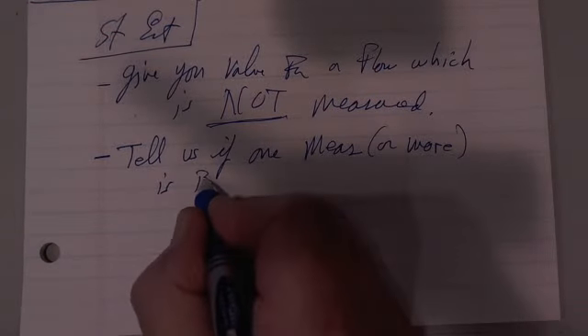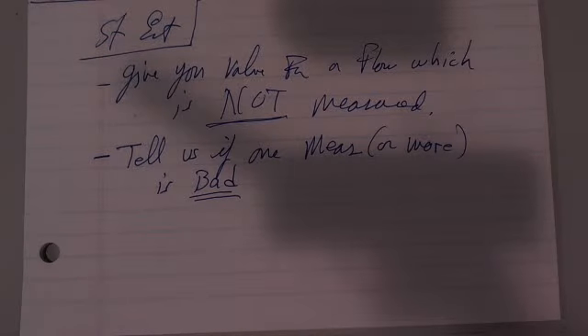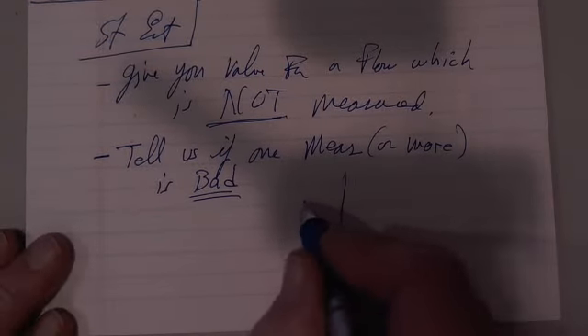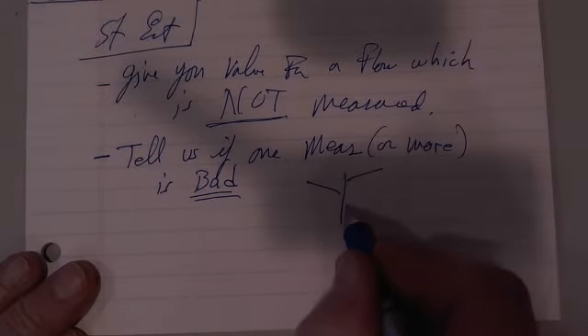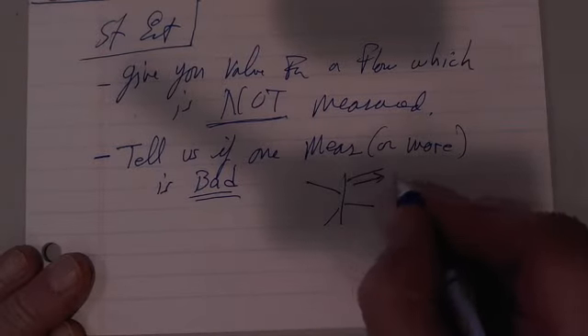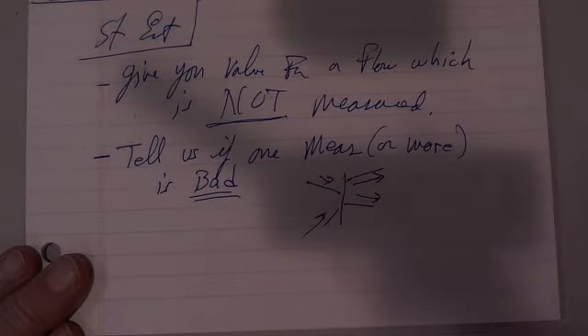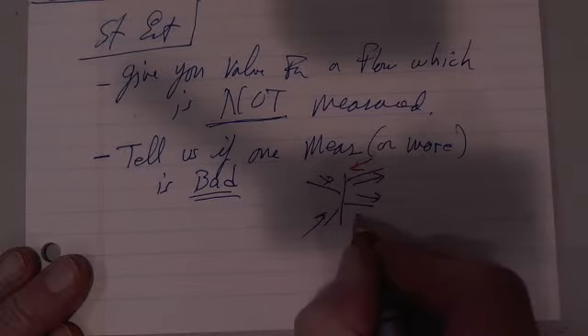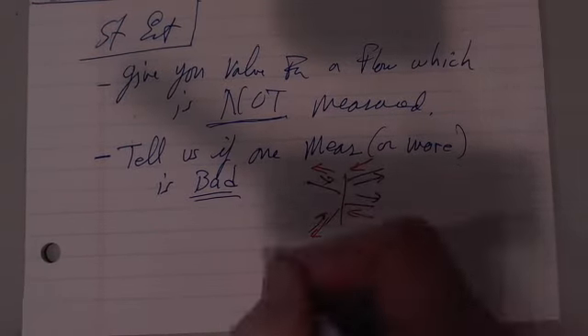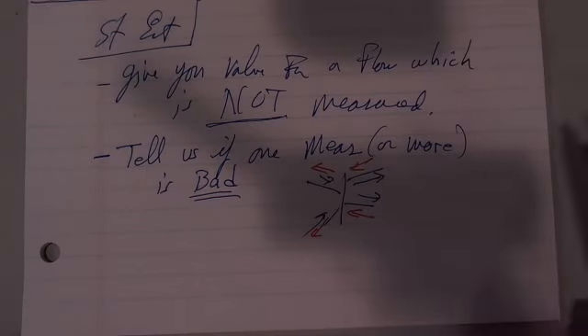I was saying last Friday, sometimes you get measurements out there in the substation that were wired up 30 years ago, and they never went out and checked everything, and it turned out they wired them backwards. It happens. You end up with a substation where you've got power flows coming in and going out, and they're supposed to be measuring flows one way, but by Jove, they're telling you the flows are the opposite way. They all add up still, but they're all negatives, all backwards, and you think, oh, that can't be. It is. It happens.